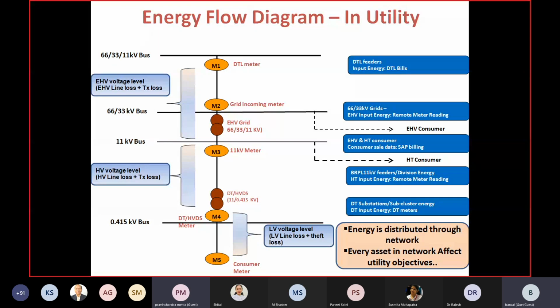If I talk about the energy flow, especially in a typical utility like ours, BSES, these utilities get power at 66 kV or 33 kV. There are a few which get power at 132 kV also. Then there are transmission networks, followed by the grid, where the signal is brought to 11 kV. In India, 22 kV is not so popular, but 11 kV is the most popular one. We call this the HT level. Then we have the distribution transformer, where the energy is further transformed from 11 kV to 440, or single phase to 3 phase.